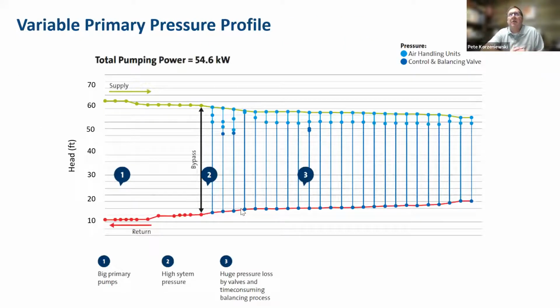So if we're going to dig into that cost, we want to look at a variable primary pressure profile for a whole system. For this diagram that you're looking at, imagine a 25-story building that's flipped on its side, and by flipping it on its side, on the left-hand side over here, we can look at the head or pressure requirement of the pumps. So if we take a cycle of our pumps in the system, before we go into the chiller, we've got our hot side here. Sorry, I'll get my laser pointer ready. We start here on the low pressure side, which is essentially leaving our chiller and entering our chilled water pumps, and the pumps doing their job are adding, in this case, 50 feet of total dynamic head to the fluid entering the system, and then we travel through the primary loop. So our primary loop is here, you see our bypass, and then return.